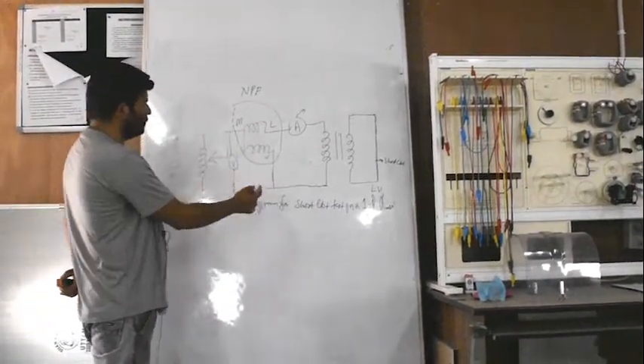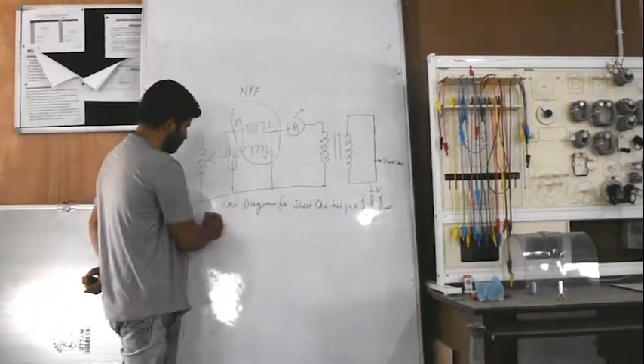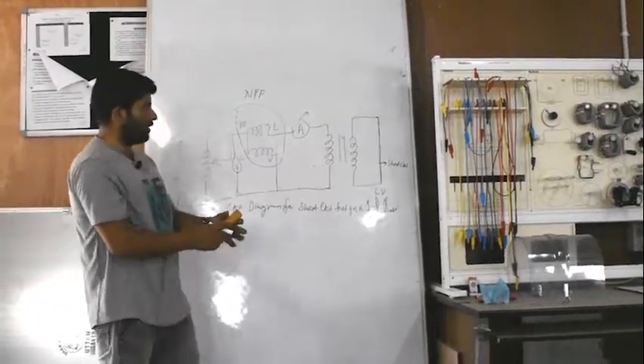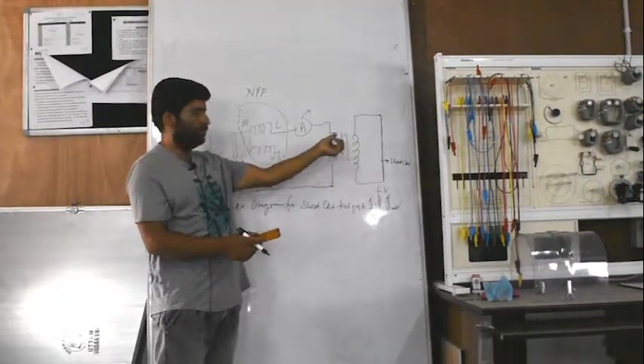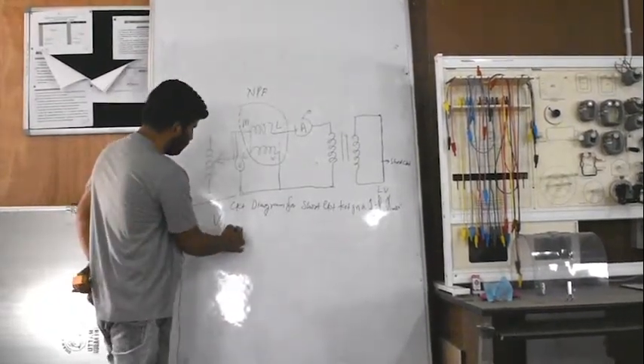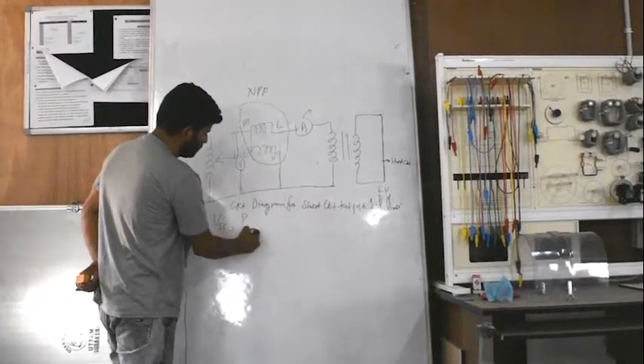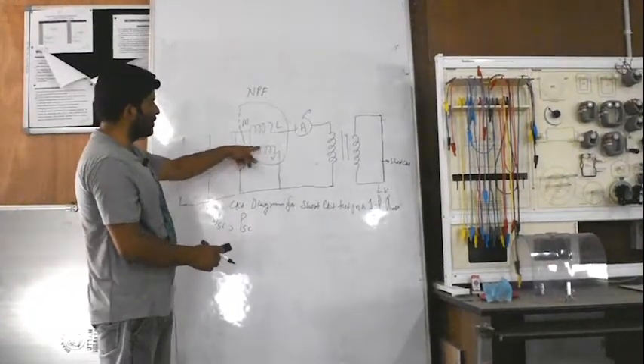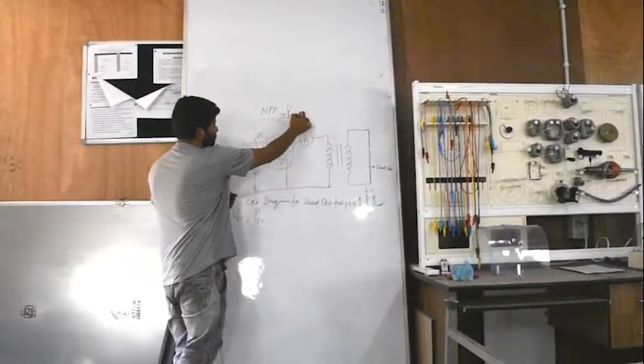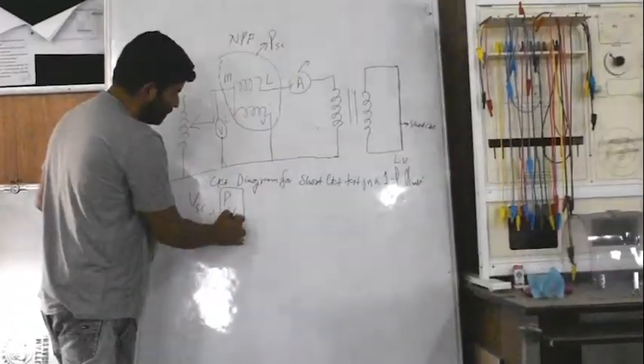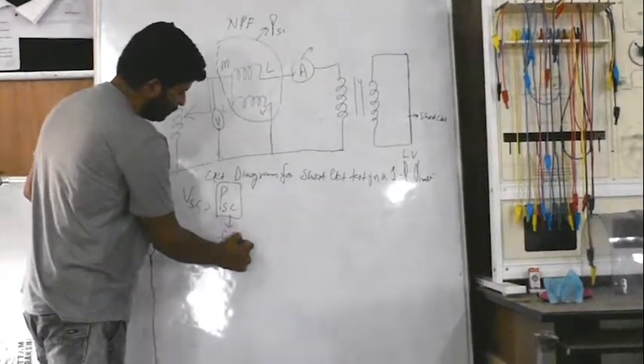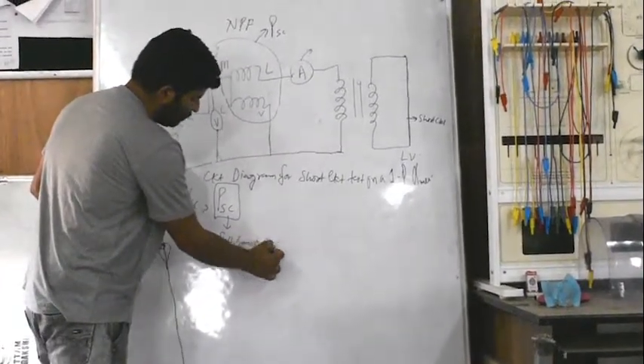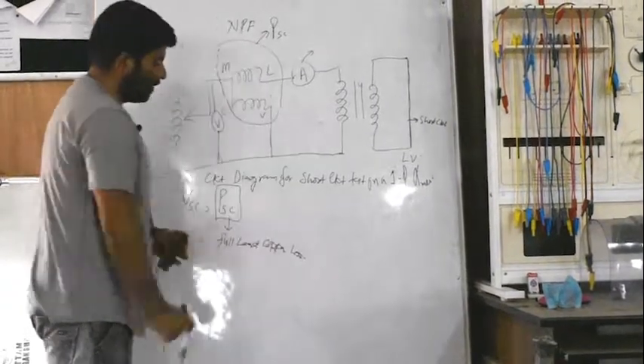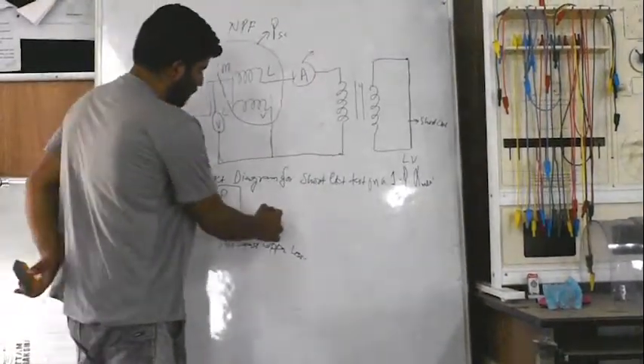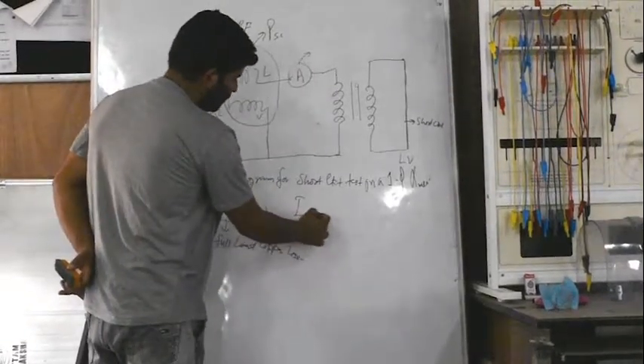Similarly, we will have three readings. We will have VSC, the short circuit voltage at which the rated current or short circuit current is flowing in our transformer winding. We will have PSC, the reading of the wattmeter, which represents the full load copper losses. And another reading will be ISC, the short circuit current flowing in our transformer winding.